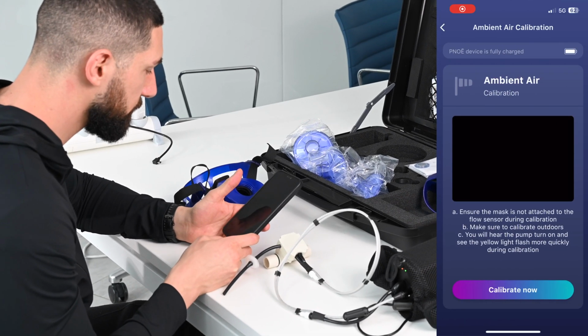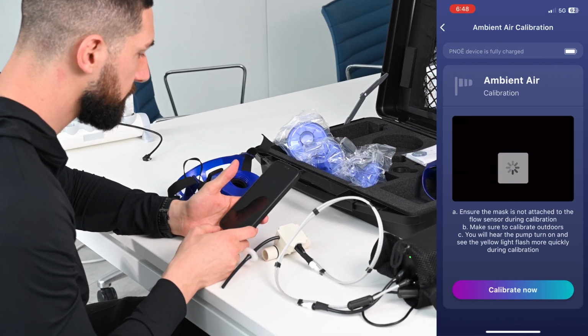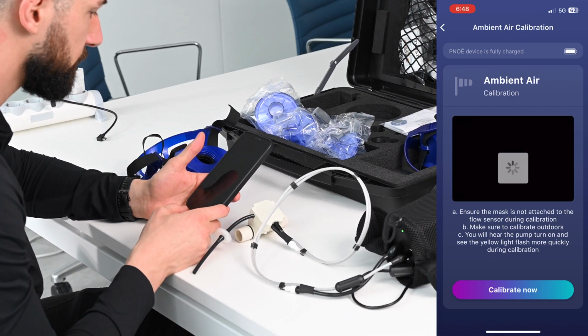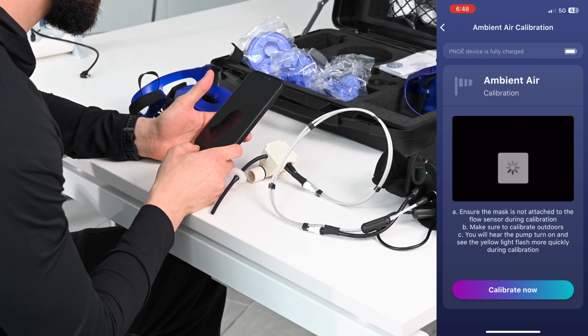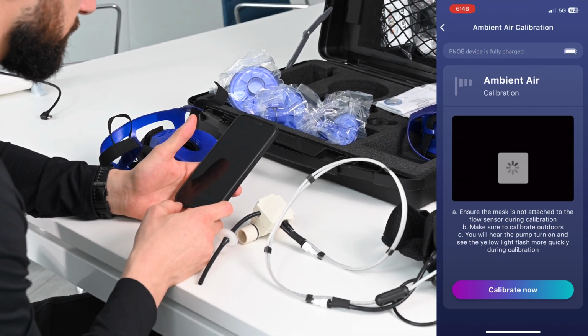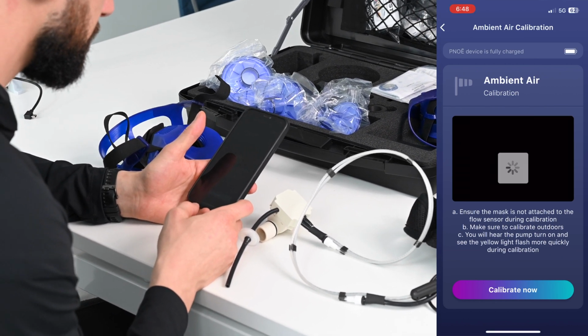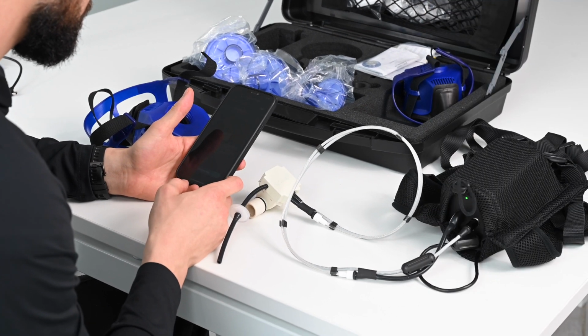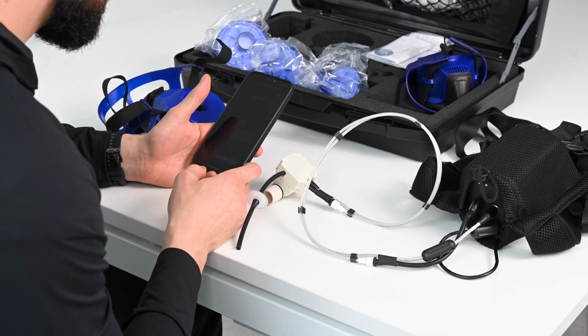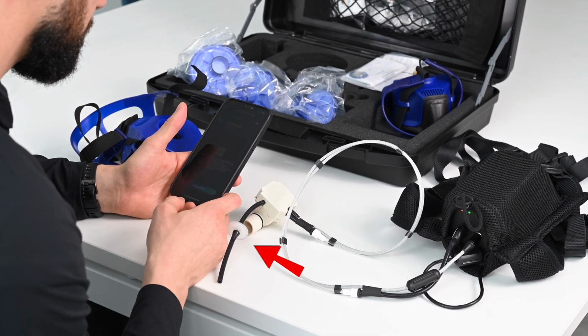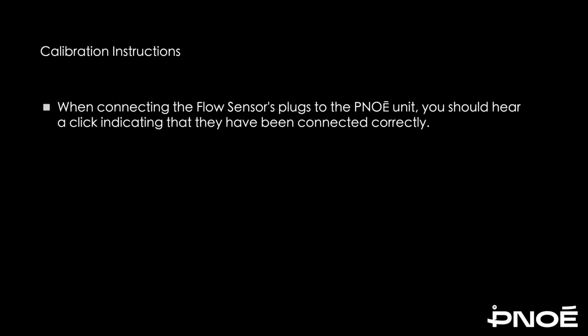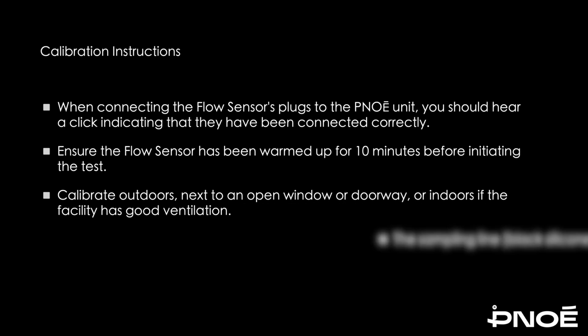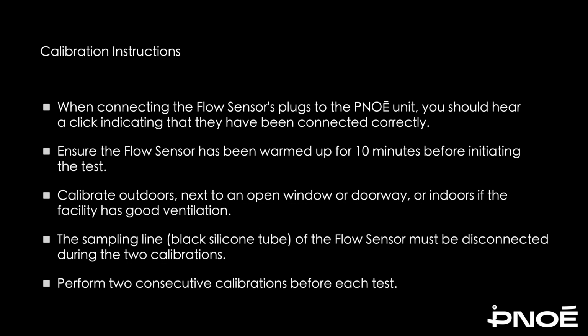To perform an ambient air calibration, you should either perform them outdoors or next to an open window or doorway to outdoor air. If the facility has good ventilation though, the calibration can be done indoors. Please make sure that the sampling line, the black silicone tube of the flow sensor, is not connected to the mask adapter when performing a calibration in order to sample ambient air. Make sure to perform 2 consecutive ambient air calibrations prior to the test.